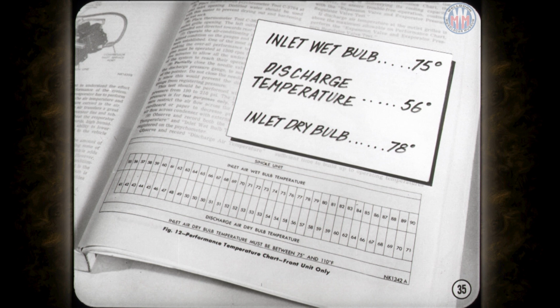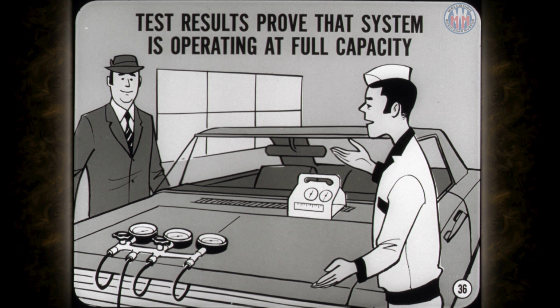Compare the figures against each other on the appropriate performance temperature chart in the service manual to determine if the system is operating properly. If the overall performance test turns out okay, it saves the need for further testing. The results also prove that the system is operating at full capacity when there's any question about cooling output during hot, humid weather.